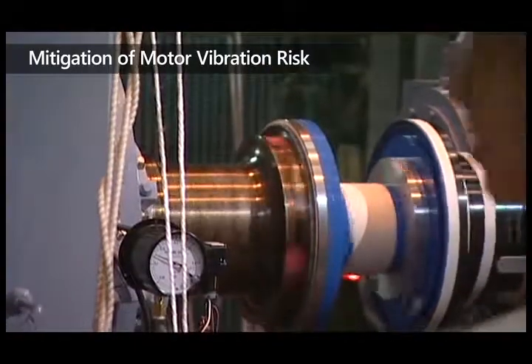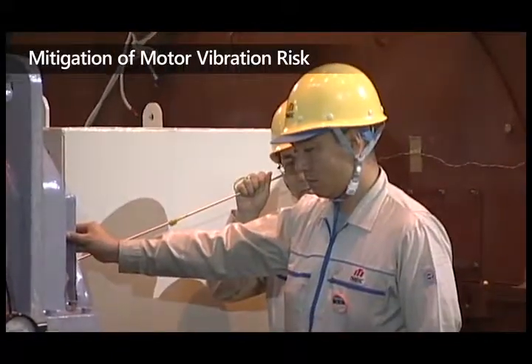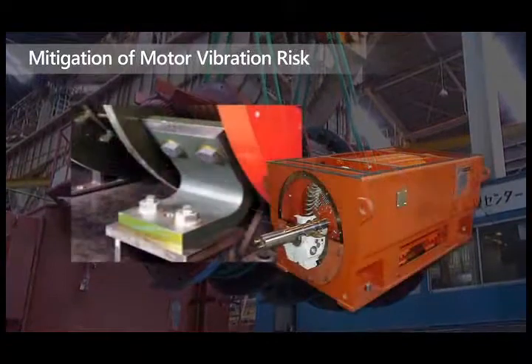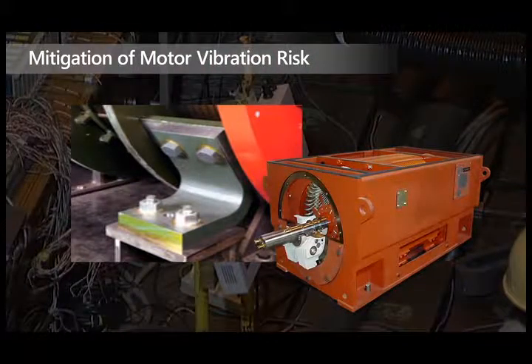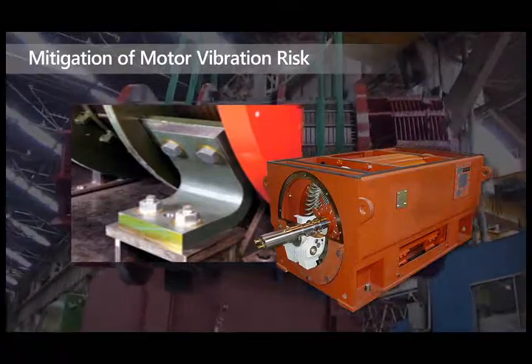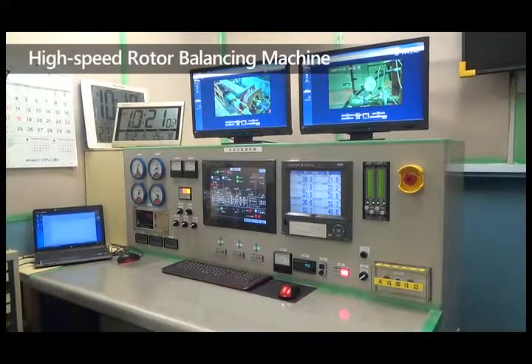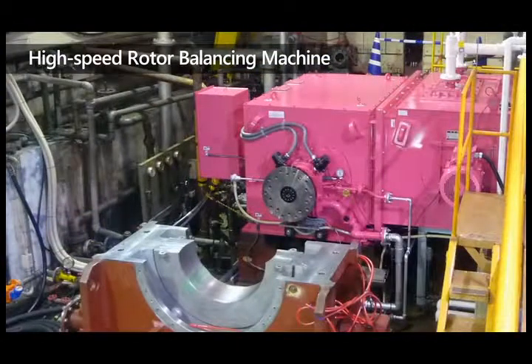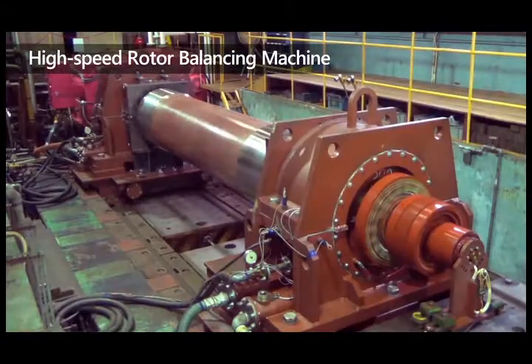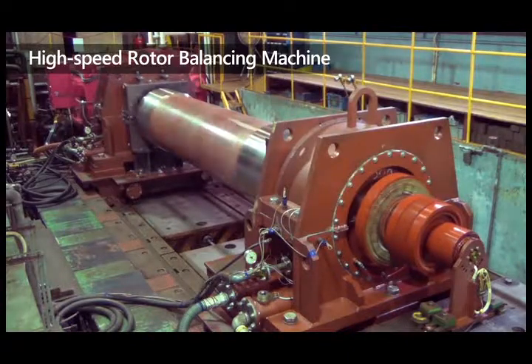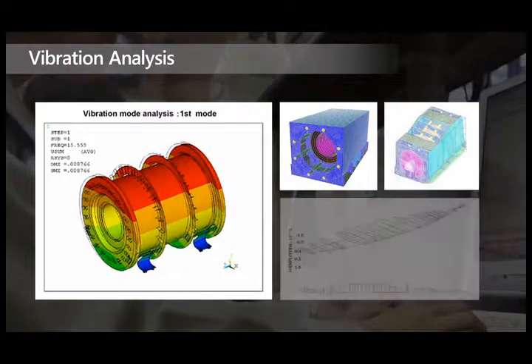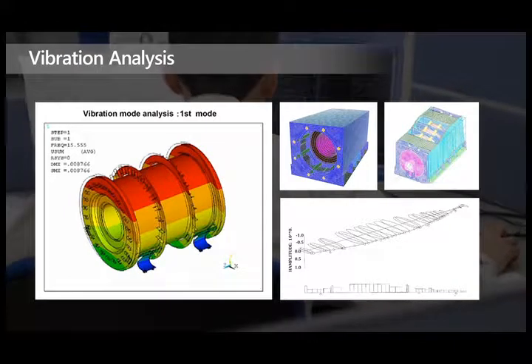In order to mitigate motor vibration risks, TMEIC takes 3 basic measures. The first one is to support stator assembly with springs. This photo shows a 2-pole motor stator assembly supported with springs. This can reduce vibration level by 50%. The second measure is a high-speed rotor balancing machine. We can perform balance tests up to 8,000 rotations per minute. The motor of the balance machine is also a high-speed motor, and its rating is 3,000 kilowatt, 8,200 rotations per minute. The third measure is the vibration analysis by computer-aided design, or CAD, of stators and rotors to minimize their vibration levels.